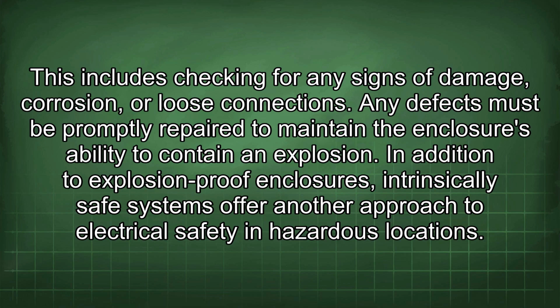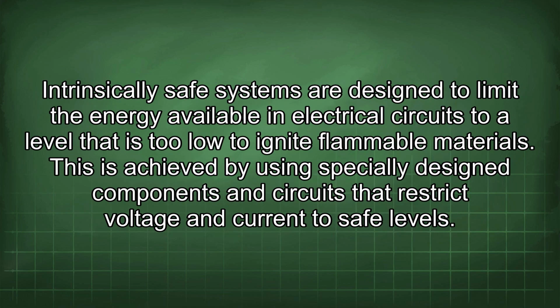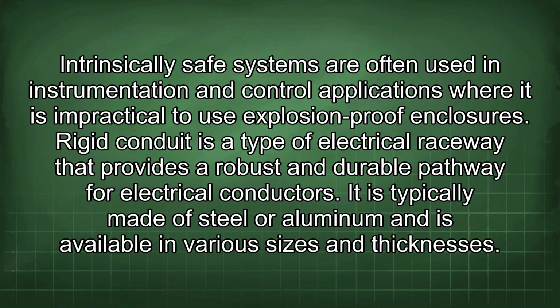In addition to explosion-proof enclosures, intrinsically safe systems offer another approach to electrical safety in hazardous locations. Intrinsically safe systems are designed to limit the energy available in electrical circuits to a level that is too low to ignite flammable materials. This is achieved by using specially designed components and circuits that restrict voltage and current to safe levels.